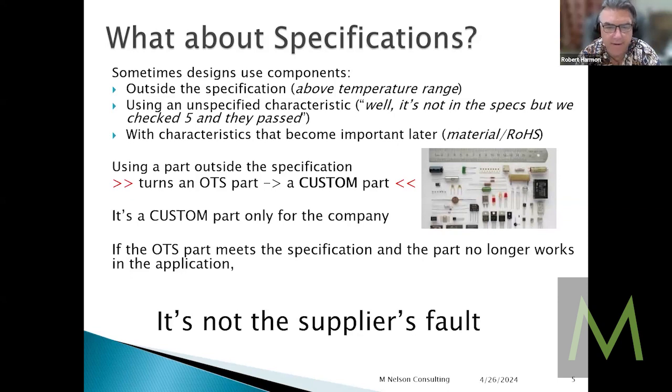Yeah, I get it. I gotta be careful. Yeah, and it is a very easy trap to fall into, because if you're getting parts that are working, even if they're tighter than the spec, it kind of looks like everything's okay. But then a change happens and it doesn't work. Right. I mean, working in the operating room, this trocar is not the equivalent of this trocar. They look the same, they act the same, but they're not the same. And the only person who really understands is the end user.